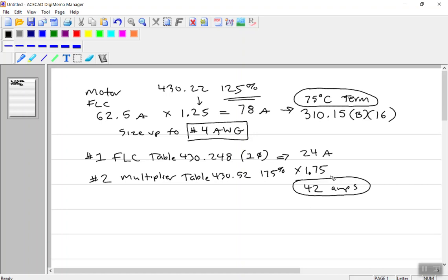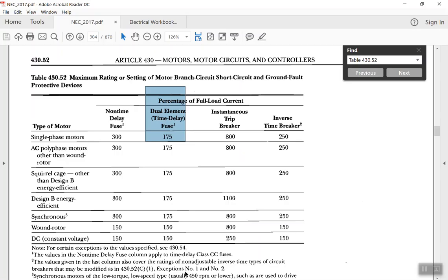We need that. Okay, but that's not a standard overcurrent protected device. That's not a standard size. So wouldn't we need to take this on over? Let's draw an arrow this way, to table 240.6, and we went there in other lectures. I think we would all agree, pretty easy to find this thing. Let's just go there real quick. Not hard to do. 240.6.